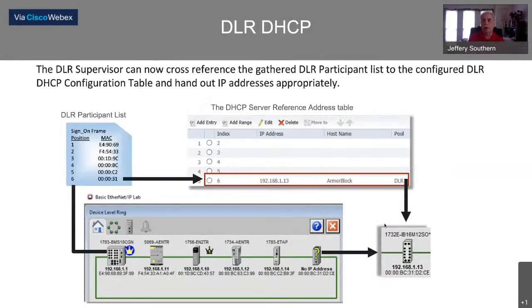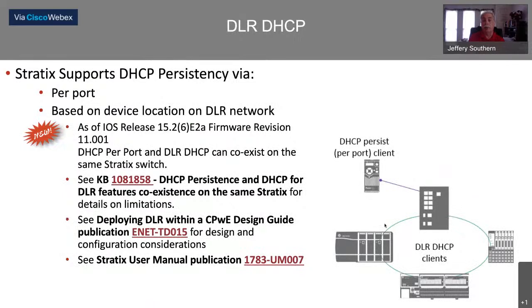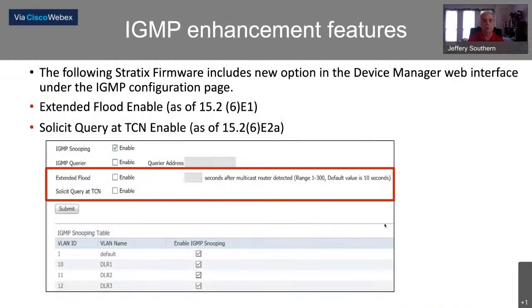This is pretty cool—no other ring supports this, to my knowledge. There are some advanced protocols for advanced rings, but timing-wise they wouldn't work within the DLR program. So this is a big deal in industrial networks: a device can get its IP address by its position in the ring. If a drive fails in the middle of the night, you don't have to worry about setting the IP address—you just plug it in and it gets it from the server or the switch.